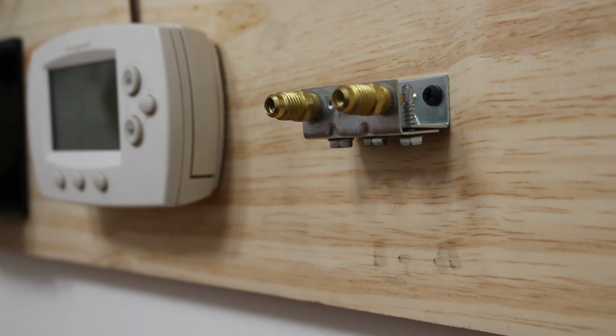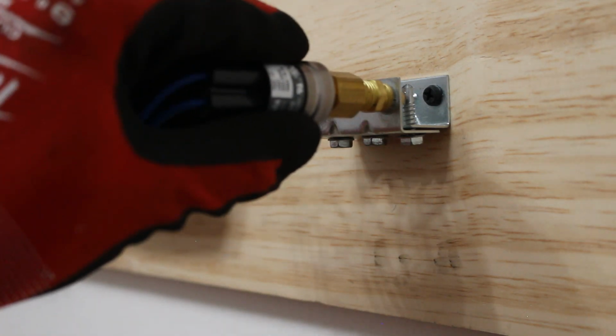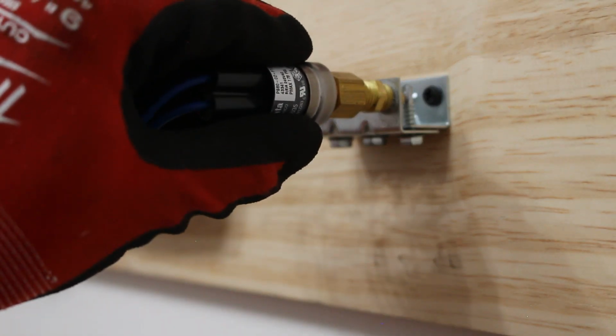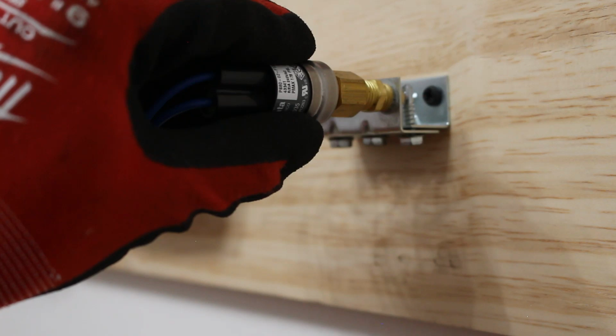Most people in the field would just install one of these onto an operating system, but personally, I like to do a good job and a safe job, as we could possibly contaminate the refrigerant just by installing one of these, as we could introduce air or moisture into the system. So preferably, I would like to recover the refrigerant, then install one of these, pull a good vacuum, check for leaks, and then wire it up.